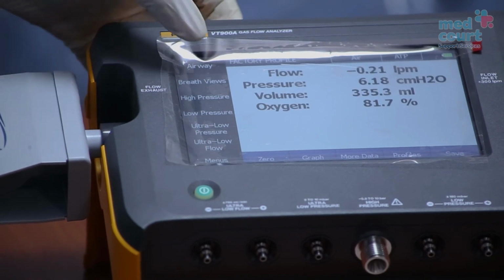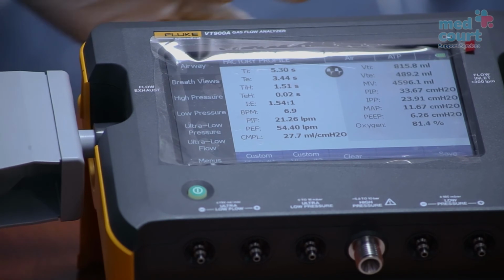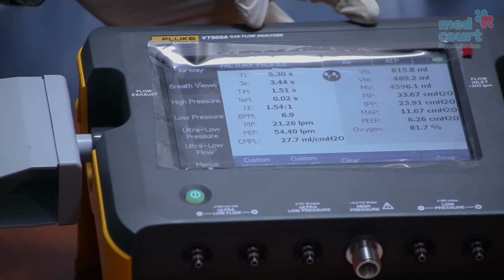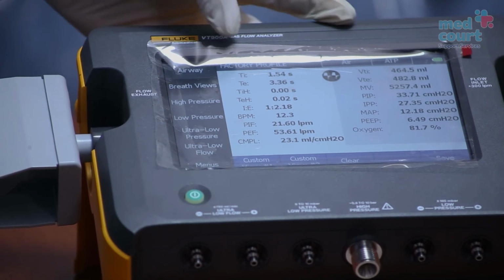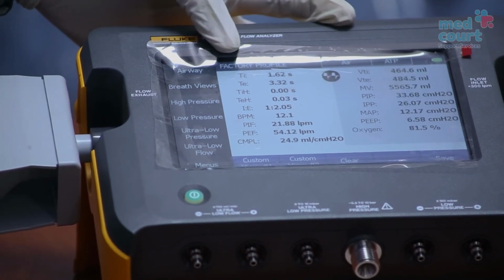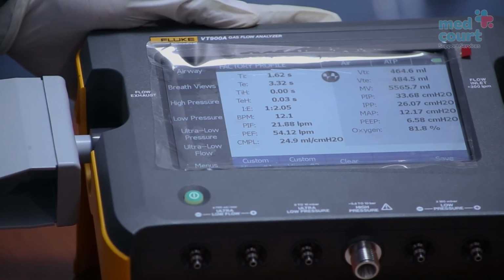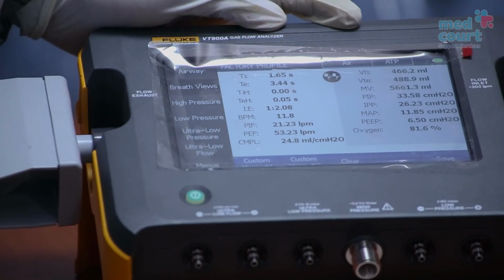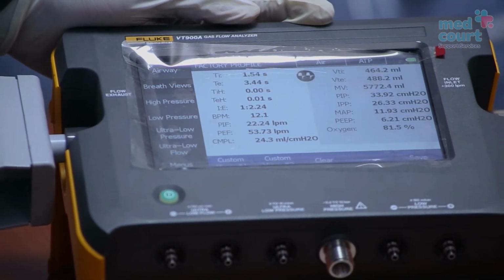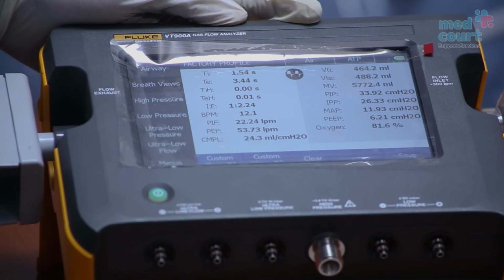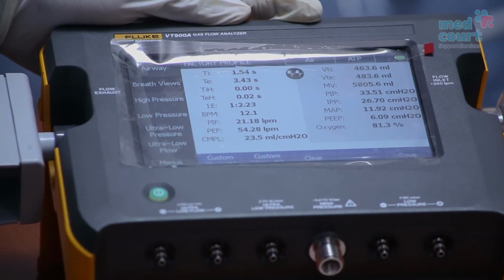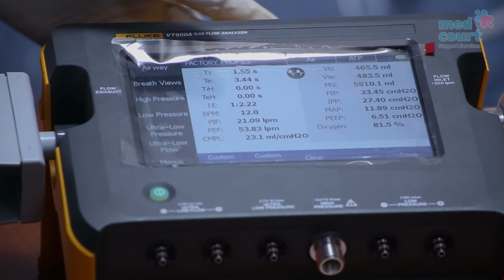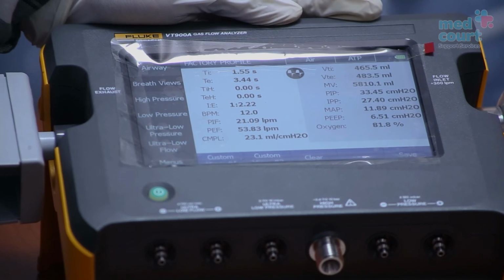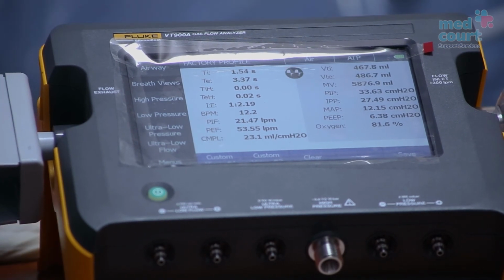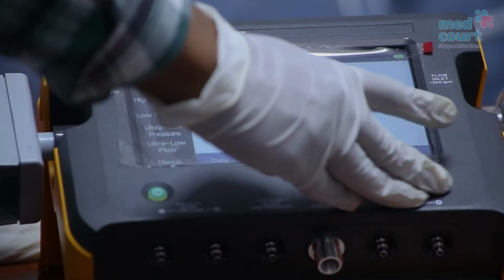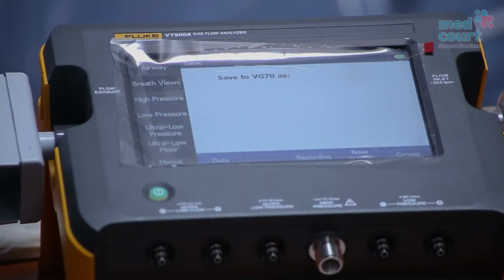The next selection is the breath view selection. Here you have different parameters, which will all be from the ventilator. You have TI, which is for inspiratory time, TE for expiratory time, TIH for inhalation time, TeH for exhalation time, IE for the inspiratory-expiratory ratio, BPM for the breaths per minute, and so on. Compare the readings here to the settings on the ventilator. Click Save. You can save as data or recording.